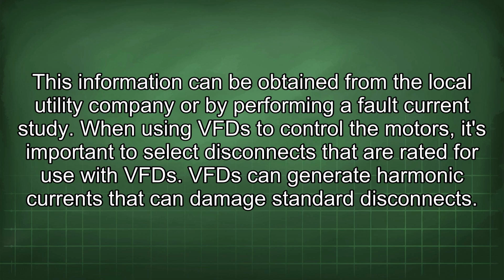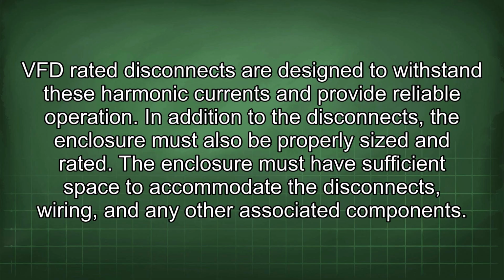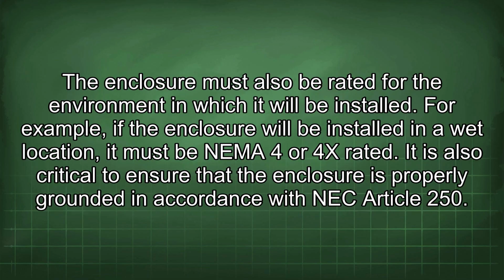When using VFDs to control the motors, it's important to select disconnects that are rated for use with VFDs. VFDs can generate harmonic currents that can damage standard disconnects. VFD-rated disconnects are designed to withstand these harmonic currents and provide reliable operation. In addition to the disconnects, the enclosure must also be properly sized and rated. The enclosure must have sufficient space to accommodate the disconnects, wiring, and any other associated components. The enclosure must also be rated for the environment in which it will be installed. For example, if the enclosure will be installed in a wet location, it must be NEMA 4 or 4X rated.